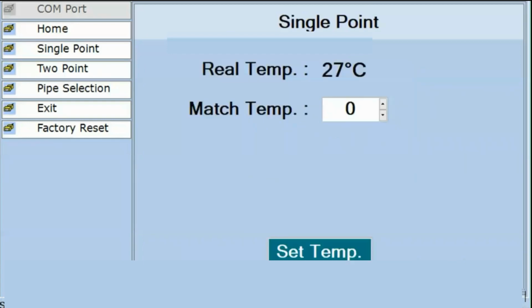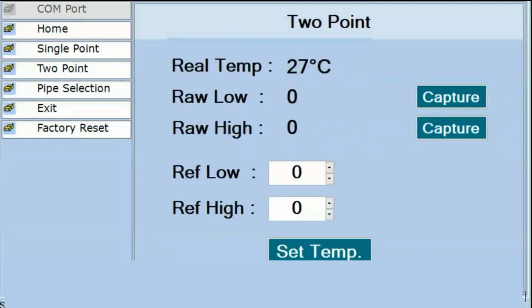We also have two point calibration, in which there are two types of temperature, you need two points to calibrate the sensor. So for the raw sensor, the reference signal you need to get using conventional thermowells to do this two point calibration, because you need some kind of initial set points to calibrate the sensor. The sensor gives approximately plus minus 3 degrees Celsius accuracy. But if you want accuracy better than 1.5 degree or 1 degree Celsius, then two point calibration is suggested.